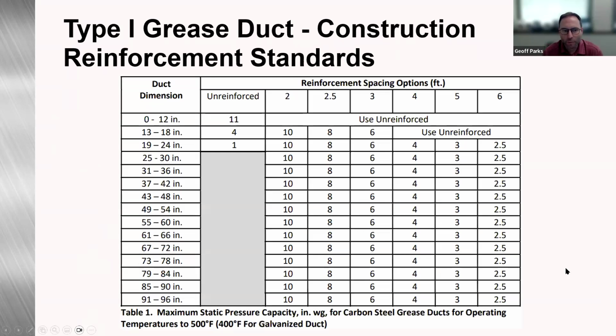So here we're looking at table 1. This is our reinforcement. So what this is, if you've ever looked at the rectangular industrial duct construction standard, the construction tables are a little bit different than the duct construction standards. So what these numbers are telling us here in the table are the inches water gauge capacity of that duct dimension at these reinforcement spacings.